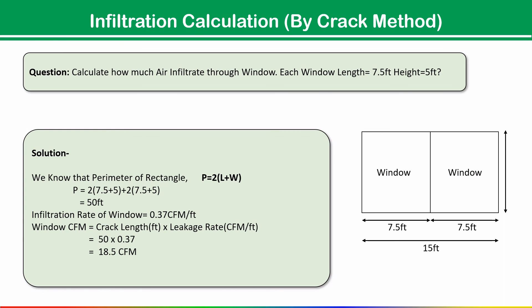The same approach applies to doors: calculate the crack length and use the appropriate leakage rate from the table for single or double doors. This covers the introduction to heat load calculation and infiltration air CFM calculation. If you are interested in complete heat load calculation using HAP software, our Udemy course is available in the description. A coupon code has also been shared — enjoy the complete course. See you in the next one.